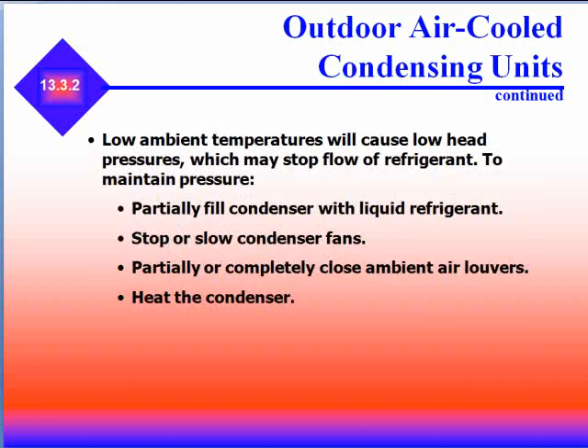Low ambient temperatures can cause low head pressures which may stop the flow of refrigerant. To maintain pressures, you can partially fill the condenser with liquid refrigerant, stop or slow condenser fans, partially or completely close ambient air louvers, or heat the condenser.